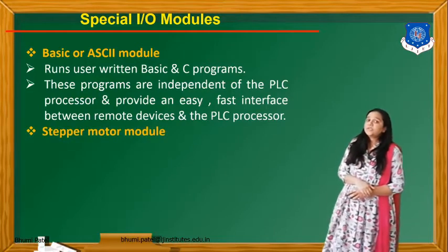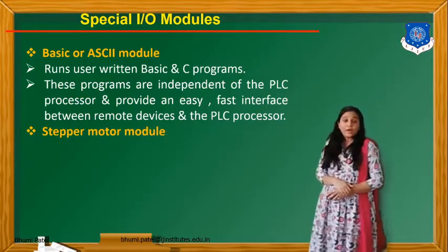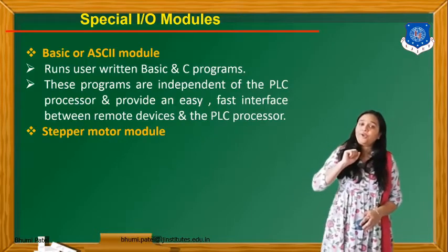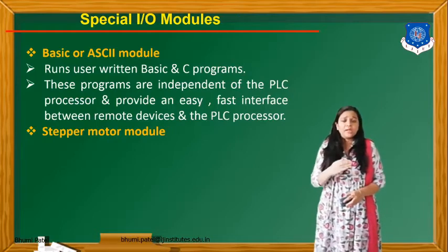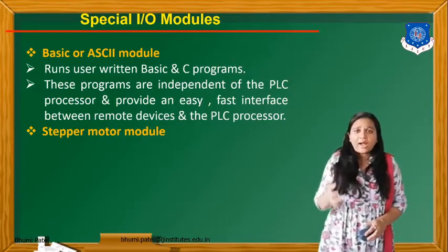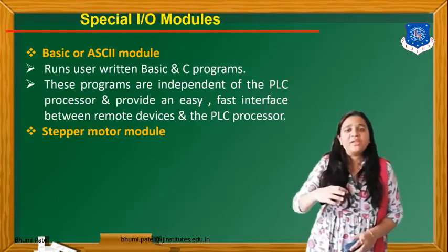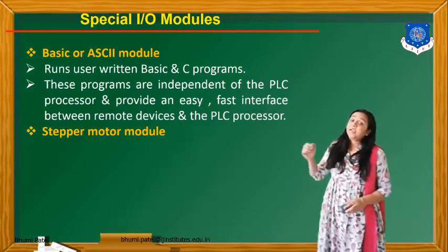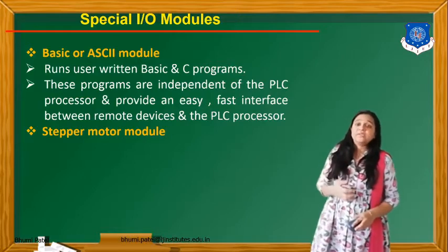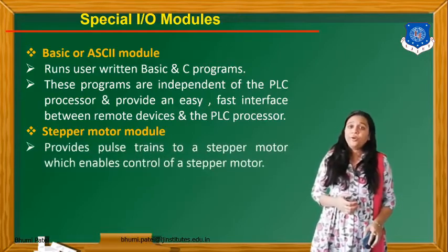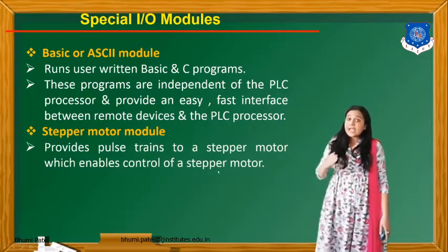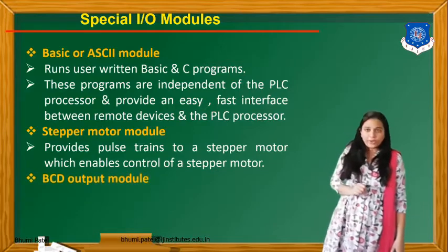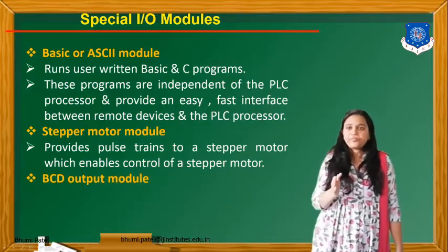The next one is the stepper motor module. Now, generally we use the stepper motor to count the steps of a particular system. Okay, if we deal with a hydraulic or pneumatic valve, and our requirement is that the hydraulic valve be open 50% or 25%, at that time we can connect a stepper motor to this device. So the stepper motor module provides the pulse train to the stepper motor, which enables the control of the stepper motor.